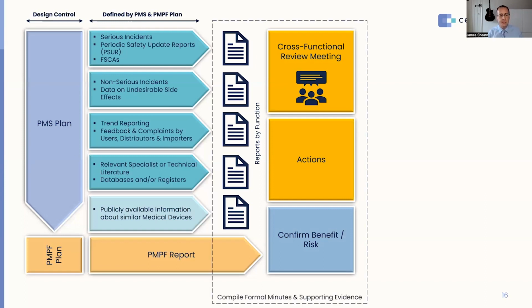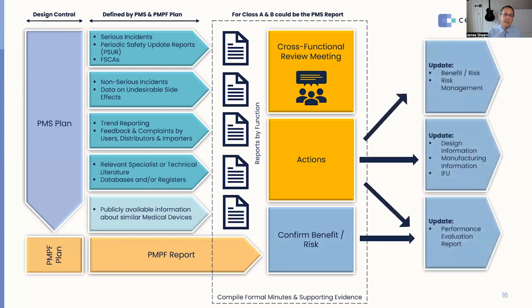So obviously that meeting is going to have a set of formal minutes and will be compiled with all the supporting evidence behind it. And if you've got a Class A and B product, that can actually be your PMS report. For Class C and D, we have other deliverables, but from the actions from that report, we can then use that to drive the updates to benefit risk, design information, performance evaluation report. And we can utilize the normal mechanisms that we have for control, so design control, change control, CAPA if need be, in order to do that.